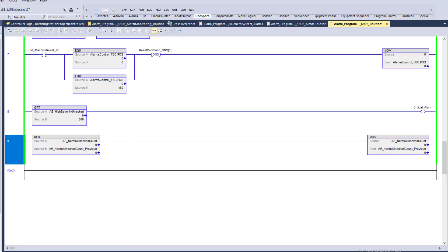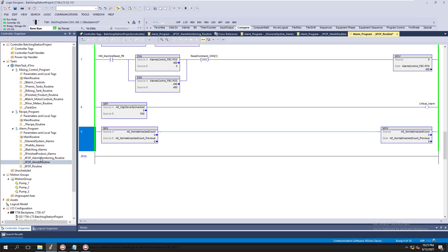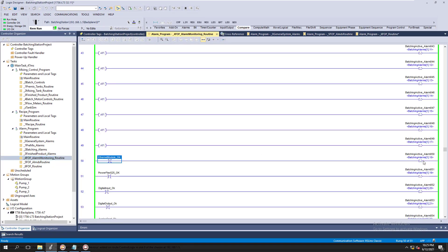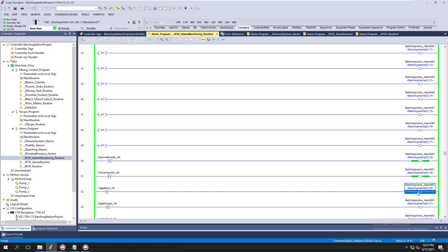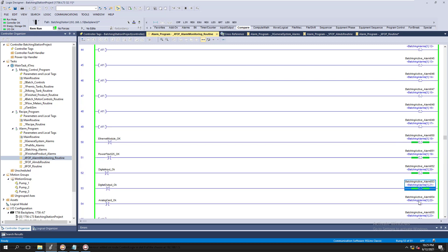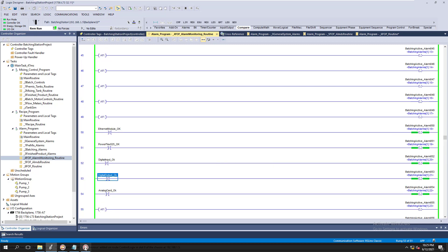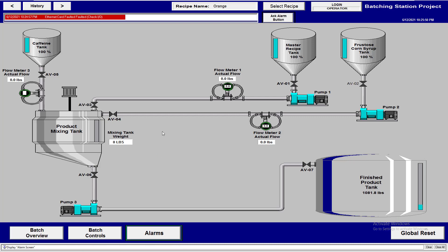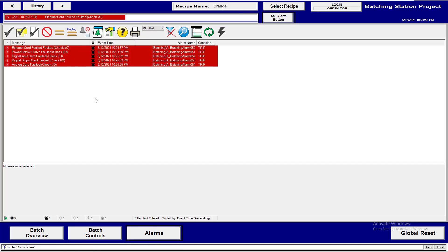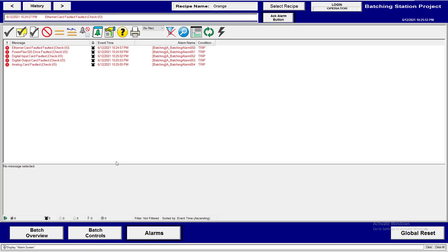Now how are we going to actually do this? We'll manually trigger an alarm — we're not going to do anything special. We'll come in here and trigger alarms like we did. Let's trigger two of them, three, four, five of them. We'll verify in our system we did get all five of those alarms. We did get all five in our alarms and events summary.